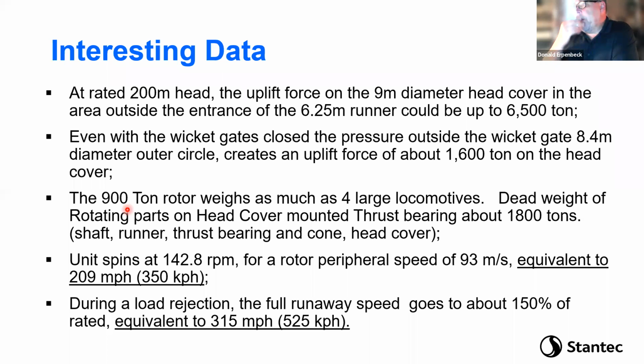Right? Some interesting data is that that turbine is 6.2 meters in diameter. It can produce a thrust of 6,500 tons on that head cover if it wasn't counteracted and the seals weren't working right. With the wicket gates closed, it still has 1,600 tons on it. And then that bolt circle is 8.4 meters in diameter. The 900-ton rotor weighs the same as 4 large locomotives. So to shoot that thing up in the air and to see the pieces you're looking at, you've really got to put them into scale. And then the other dead weight's about another 900 tons for the different pieces. So it's about 1,800 tons of dead weight.